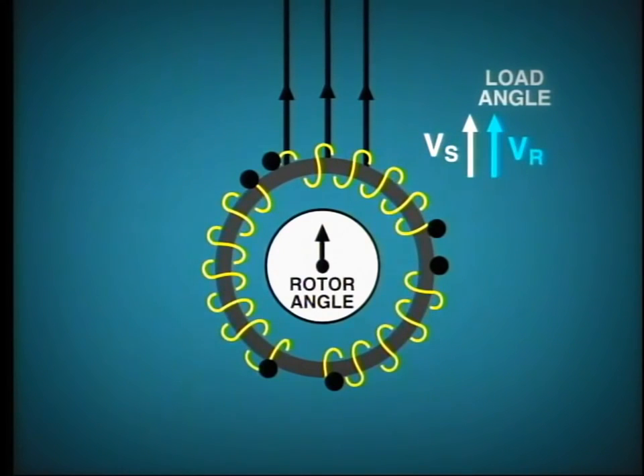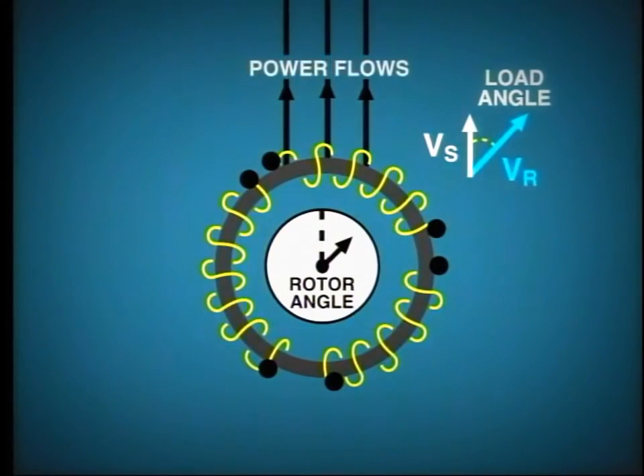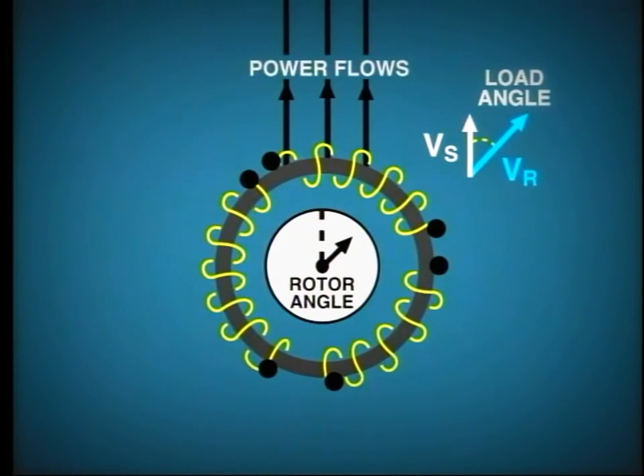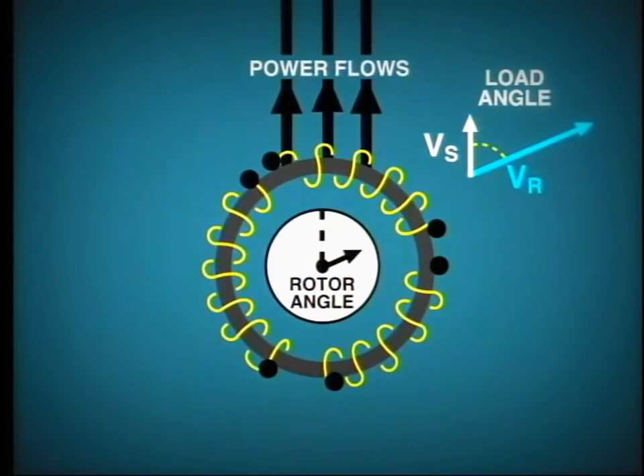The rotor and the stator voltage are exactly in phase. If we wish to increase the load output from the unit, we add more energy to the prime mover. This initially accelerates the rotor so that it moves ahead in phase. There is now a power angle or load angle created between the rotor and the stator voltage. This, in turn, causes power to flow from the generator into the system. To further increase power output, we increase steam flow and so further increase the load angle, which in turn increases the power output.